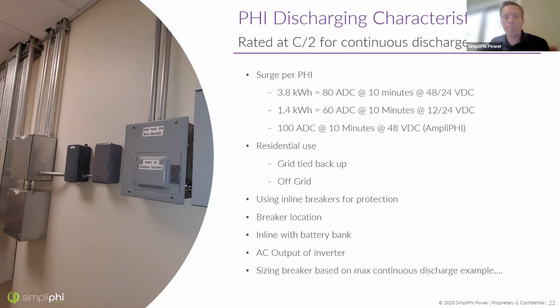AC output of the inverter is important, right? Look at the max continuous output of the inverter. Even if your customer tells you, hey, I'm really not going to use many loads. Well, once they realize that their solar energy is coming in for free and that their inverter is powering loads, they start plugging in extra equipment and using energy more. My boss tells me that energy demands from customers always change, right, once they start using renewable energy. So keep in mind that you need to size based on the output of the inverter, not on what your customer tells you they're going to plug into the wall.